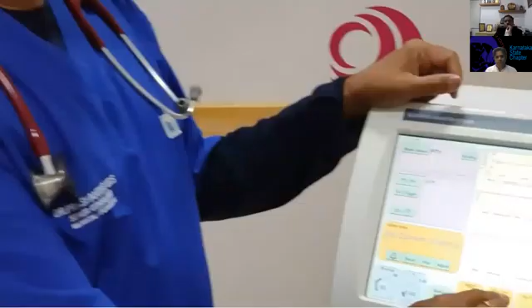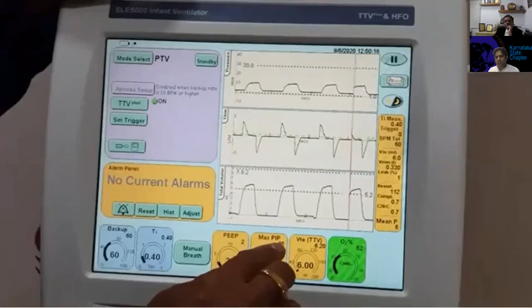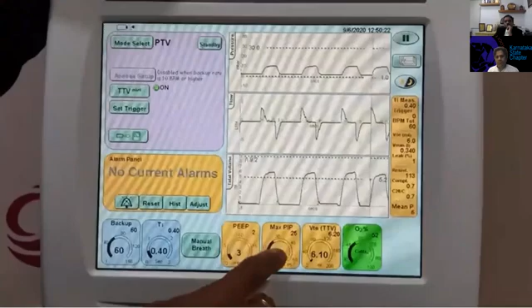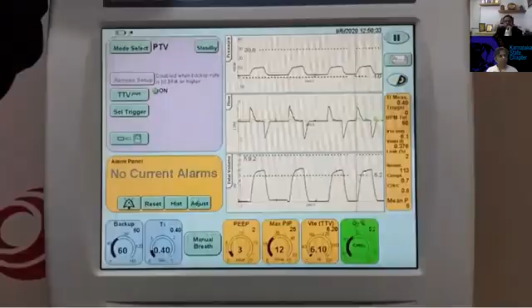It is able to do that because, by assessing the volume during the expiration, the ventilator will sense the amount of pressure it has to deliver to achieve that tidal volume. For that reason, what you see here outside the curve is what we have set, that is 25, but the baby is getting only 12. The ventilator has sensed that to achieve the tidal volume you have set at 6, it is enough to give a pressure of 12. So this is the indication that the baby is getting sufficient volume. The ventilator will see to it that the baby gets the set volume.